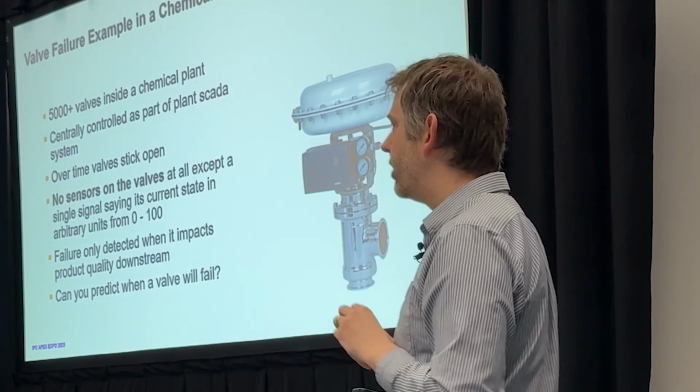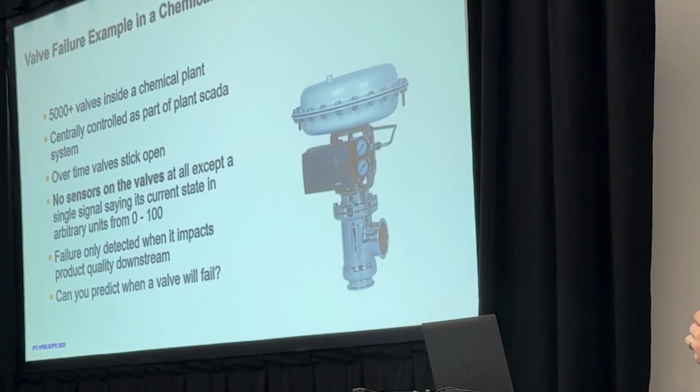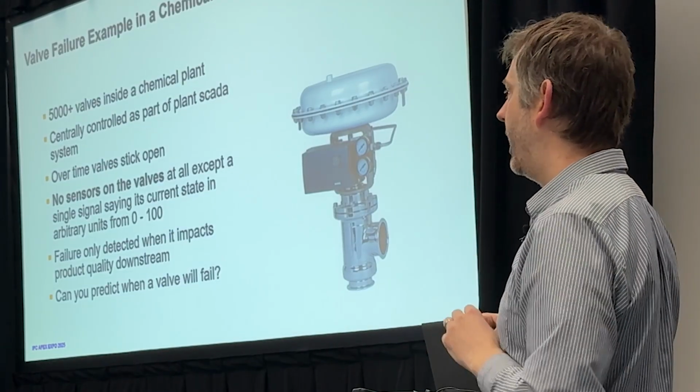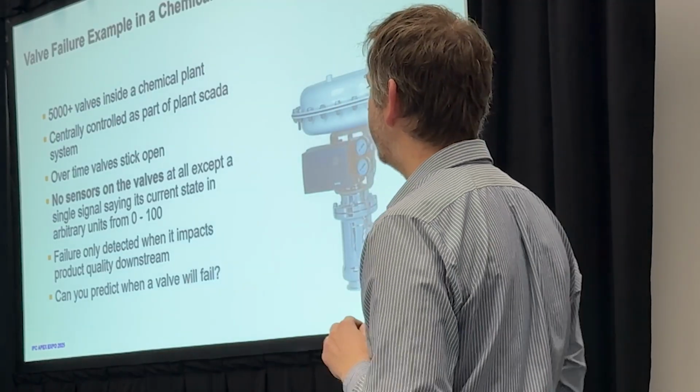But the valves have no health sensor. You don't know when they're going to break. But they break on occasion. And the failure is only detected once it impacts the downstream product quality. So the question is, could you predict when a valve would fail?